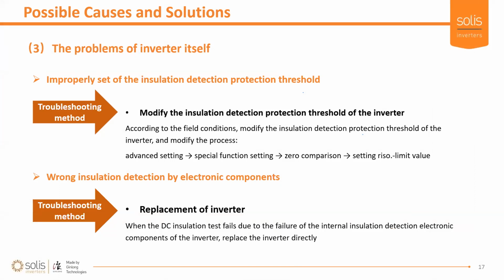The final reason you could be getting this PV isolation or ground fault is inside the inverter. If the detection circuit is faulty, as I alluded to earlier, if your earth reference is floating, which is actually not really the inverter's fault, it won't be able to detect that fault, and you just need to make sure that the connections are properly made towards your AC earth. Or if the MOVs inside the inverters are making a connection through to earth, you will see this fault.